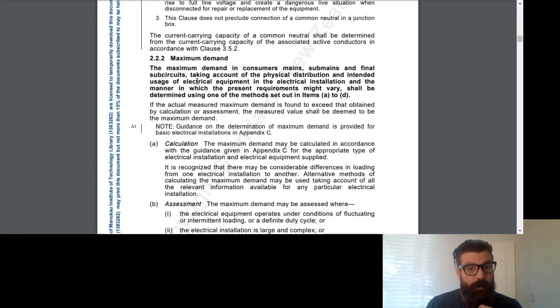2.2.2 is maximum demand. The maximum demand in consumers' mains, sub-mains and final sub-circuits, taking into account the physical distribution and intended usage of electrical equipment in the electrical installation and the manner in which the present requirements might vary, shall be determined by one of the methods set out in items A to D. So what is maximum demand? Maximum demand means how much power is this electrical installation going to consume at any given time? What's the most that it will ever use?